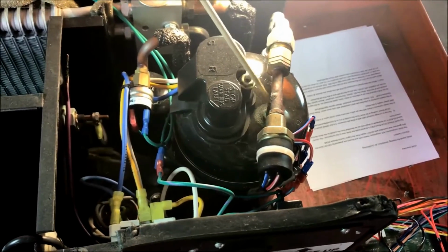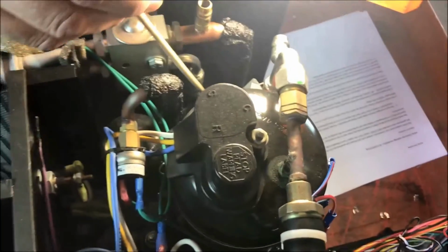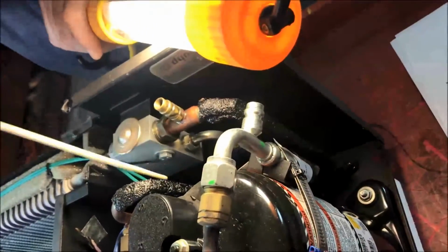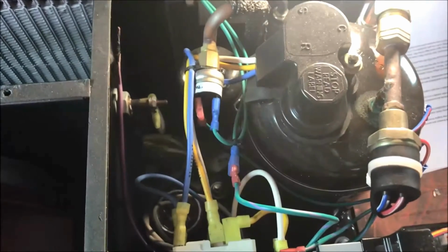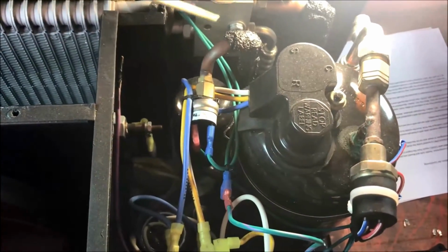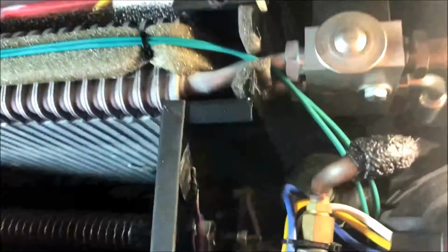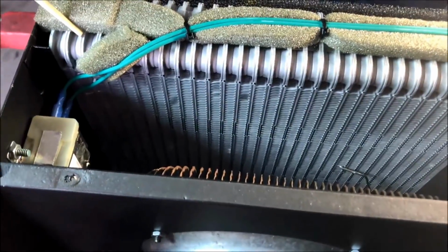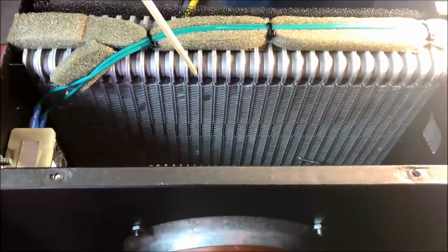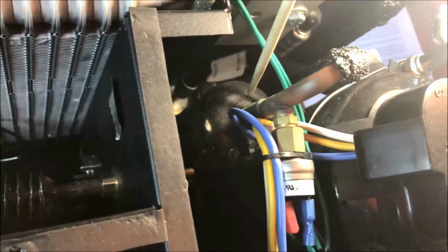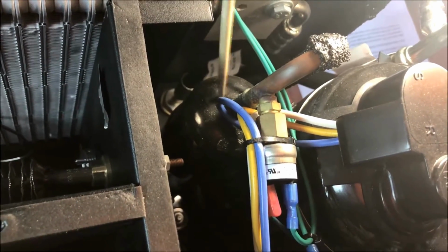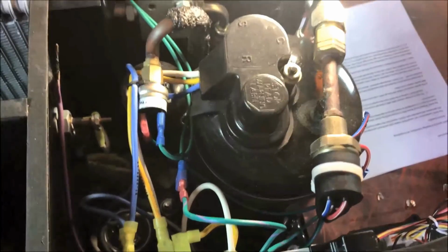It starts here. This is the discharge line. The refrigerant flows out to the condenser, goes through the condenser, turns into a liquid, and comes back to the HVAC. It comes up through the floor into the expansion valve. The expansion valve meters it into the evaporator, and then it returns to the accumulator on the compressor. This will make sure it vaporizes back to a vapor and into the suction of the compressor, and then starts the cycle all over again.